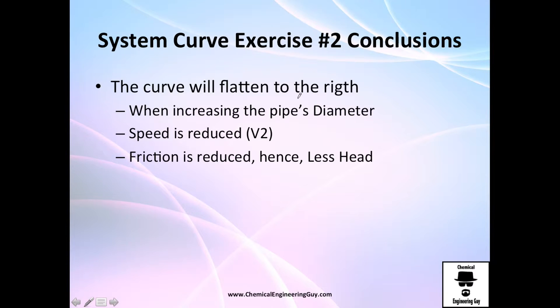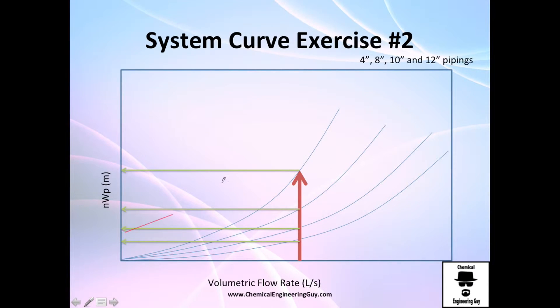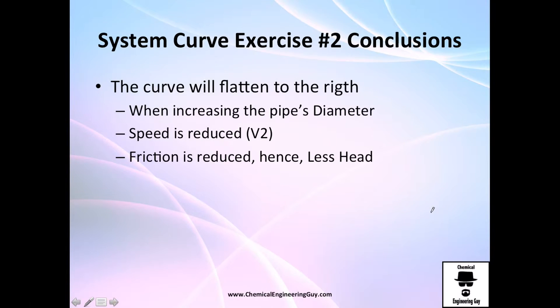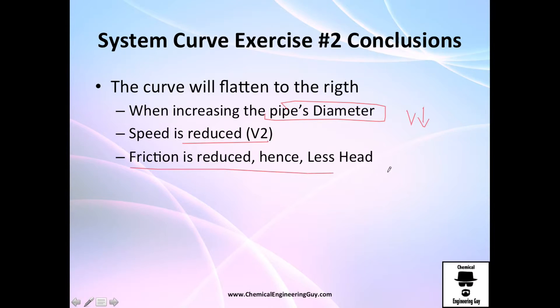The conclusions: the curve will flatten. As you can see, the four inch curve is very steep and the larger pipe curve is very flat. The system curve will shift when increasing the pipe diameter because velocity is reduced. And since velocity is reduced, friction is reduced, and therefore the amount of energy required will also reduce.